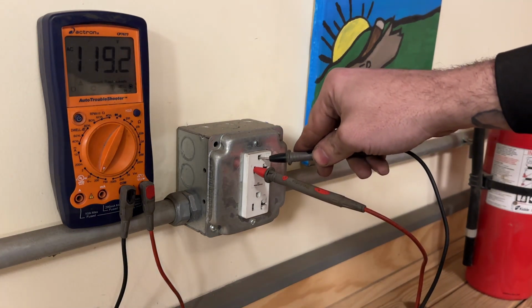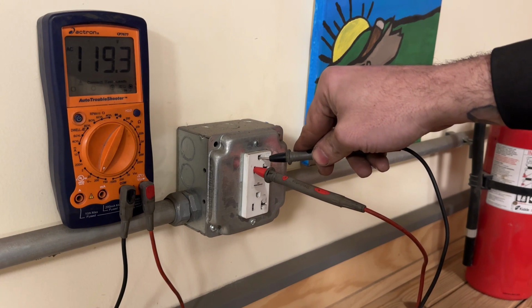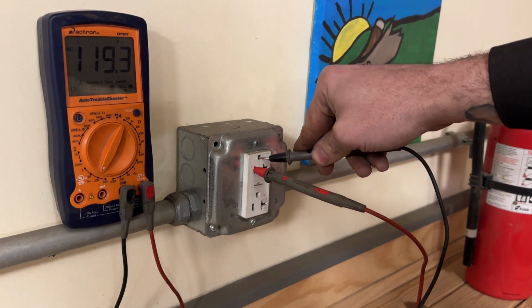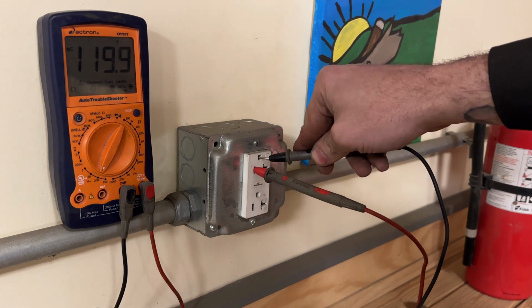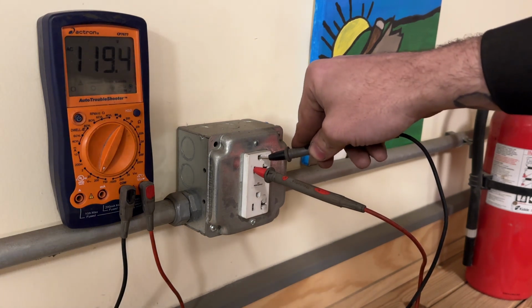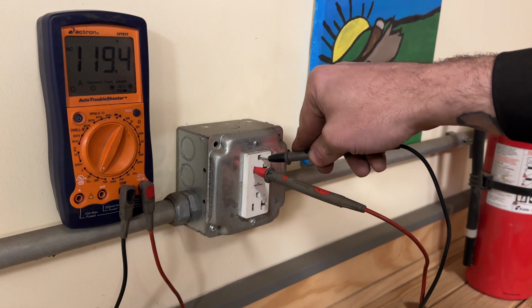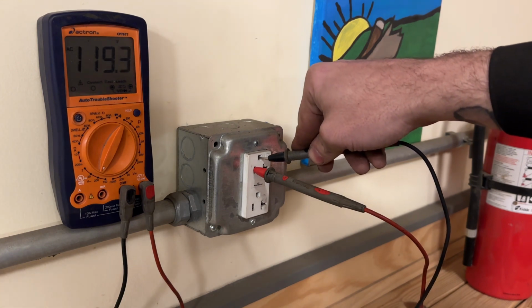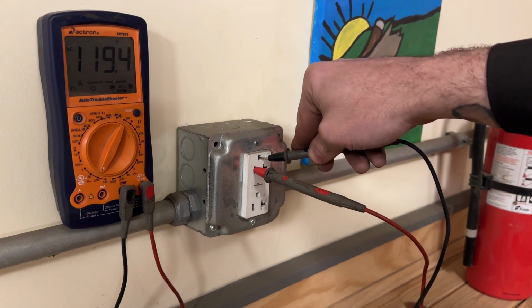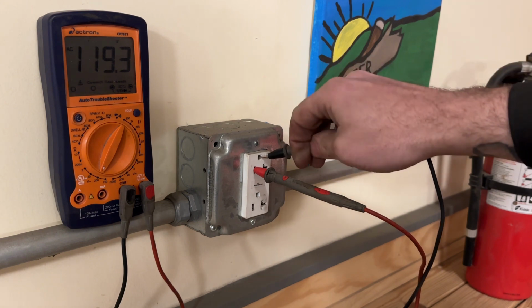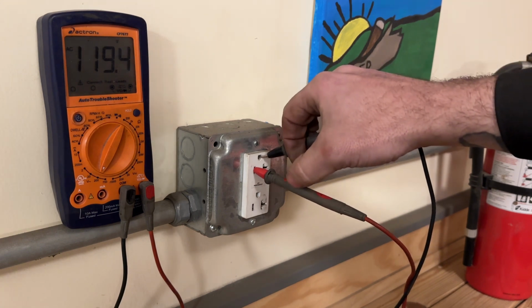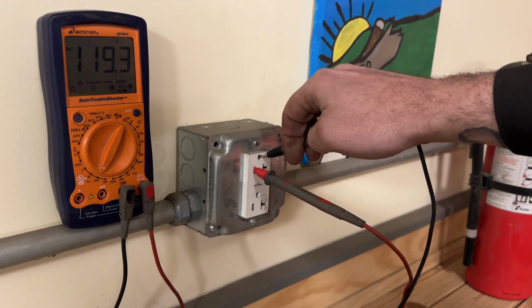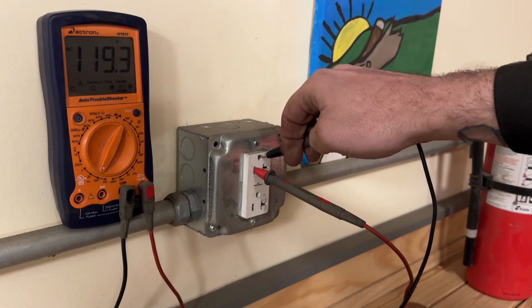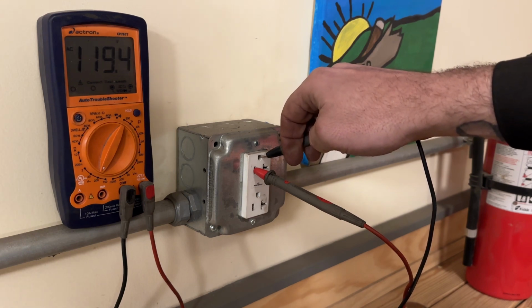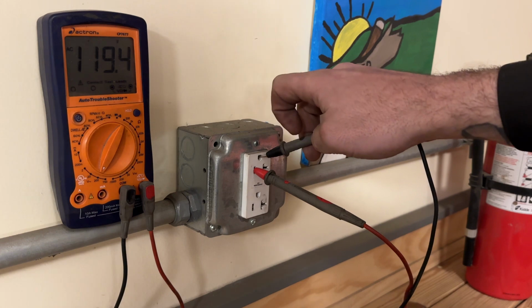So if you look there, my voltage here, being that it's at night and the power company is probably producing a fairly high voltage with nobody using any, my voltage is at 119.4 volts, higher than normal. During the day, it's about 115, 114. That's reading from the positive to the ground, so I know the ground is actually hooked up on my electrical service, otherwise I wouldn't have a reading.